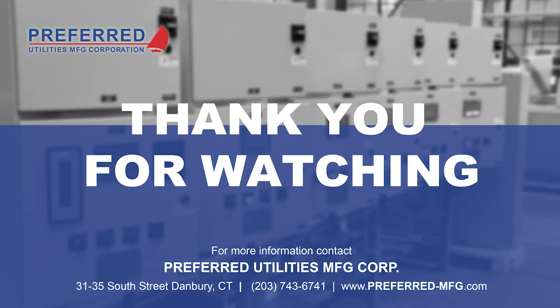How would you deal with the fuel oil return line coming from multiple generators on a roof to multiple bulk storage tanks in the basement? Can you valve or solenoid control the return line back to a specific tank? Code says must be free flowing. This is a really good question. The code that we're trying to follow here is NFPA 37, and NFPA 37 is written around gravity return.